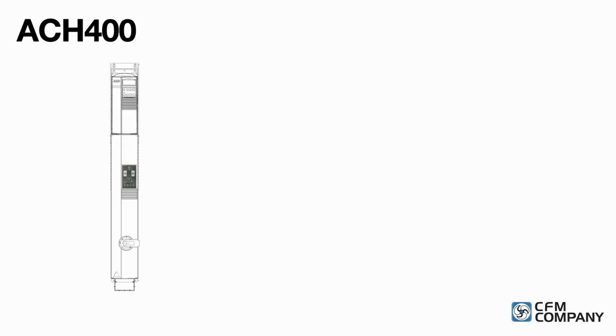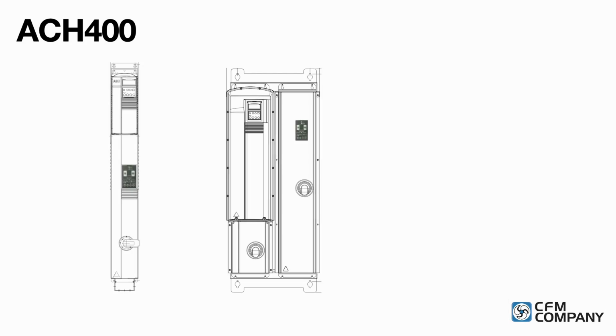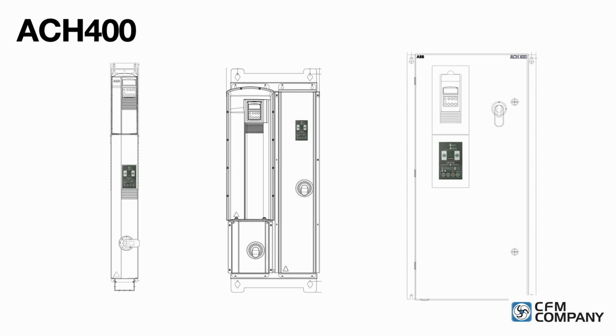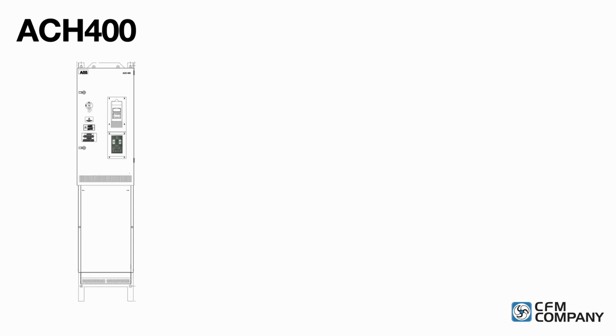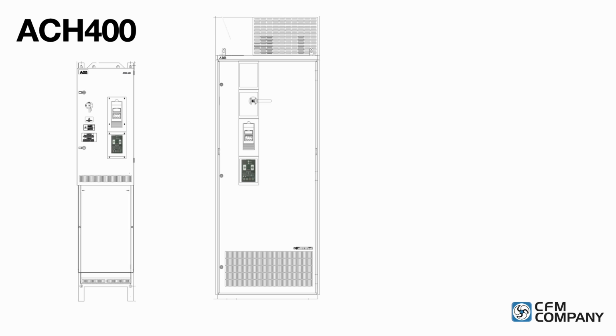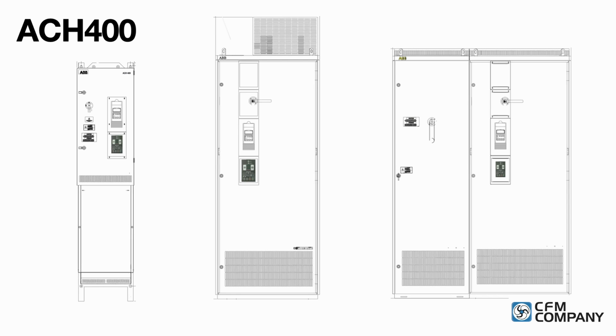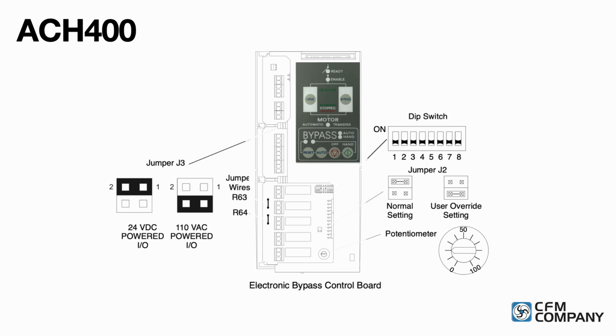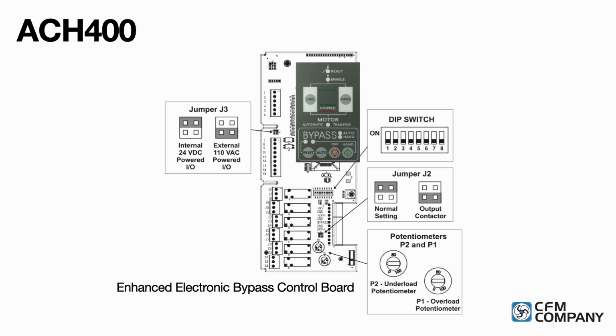To start, let's begin with a brief history of the ABB electronic bypass. Starting in 1998, ABB introduced the new ACH400 drive and the new electronic bypass option. The electronic bypass offered a standardized product across all the horsepower ranges and input voltage types. After several years of production and feedback from use in the field, ABB updated the bypass control board with a revision known as the Enhanced Electronic Bypass.